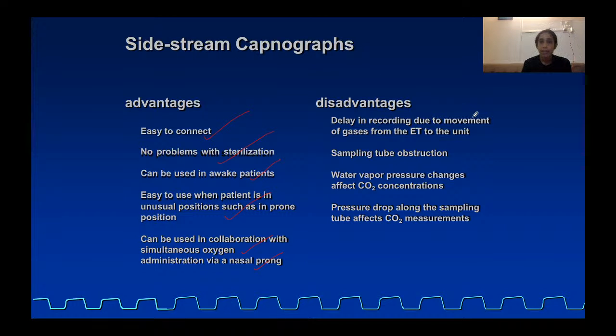The disadvantages are that there is a delay in recording due to movement of gases from the ET tube to the unit. But it is not a very significant delay. Sample tube obstruction can actually occur. Like I said, it is placed after the filter, so if secretions clog the filter, the tube can get obstructed, then there will be no reading, and you might think that it is disconnected. Any small cuts in the sample tube, since it is a very thin tube, will also give an erroneous reading. The capnography reading might be reduced and you will think that something is wrong.